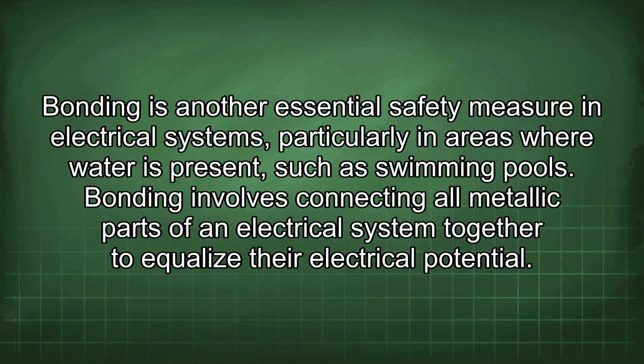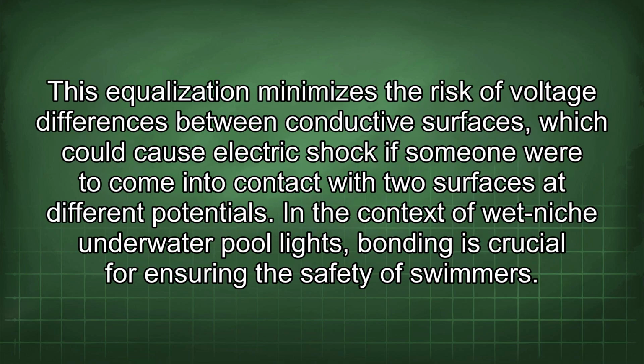Bonding is another essential safety measure in electrical systems, particularly in areas where water is present, such as swimming pools. Bonding involves connecting all metallic parts of an electrical system together to equalize their electrical potential. This equalization minimizes the risk of voltage differences between conductive surfaces, which could cause electric shock if someone were to come into contact with two surfaces at different potentials.